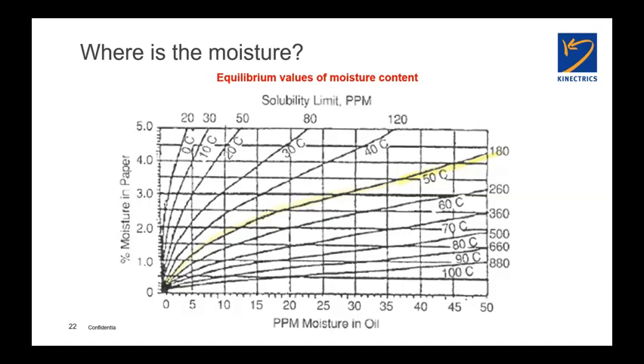Why? Because transformer loads are not constant. And even if the load is fairly constant, the operating temperature during the day, we have higher daytime temperatures, lower nighttime temperatures. We have hotter temperatures in the summer, cooler in the winter, etc. You get the picture. So they're in a constant state of flux. However, it's still instructive to look at what these curves tell us.